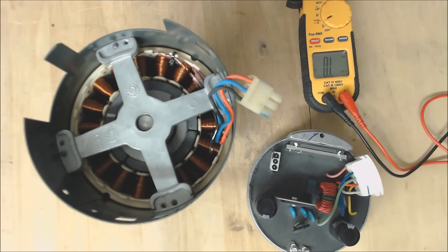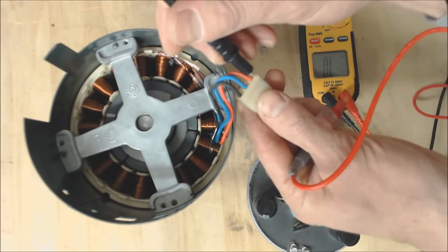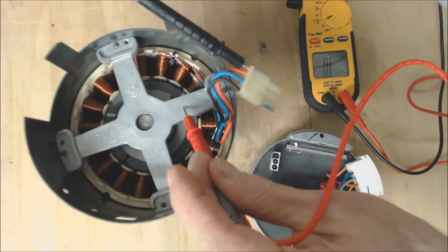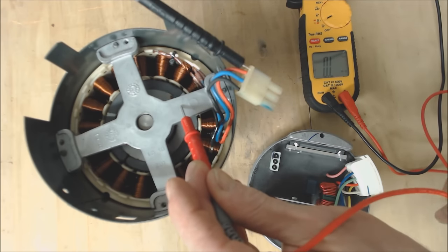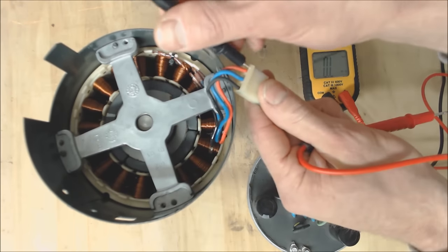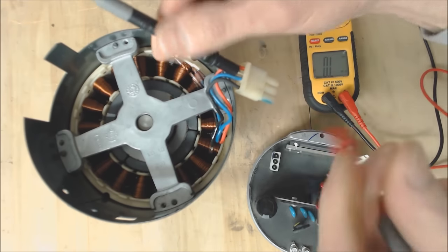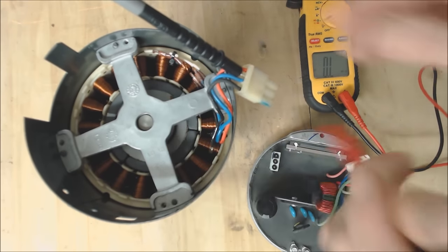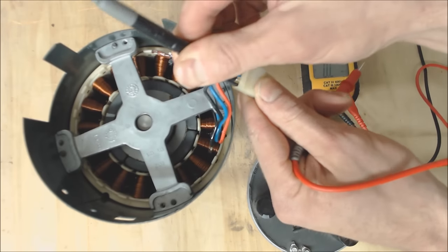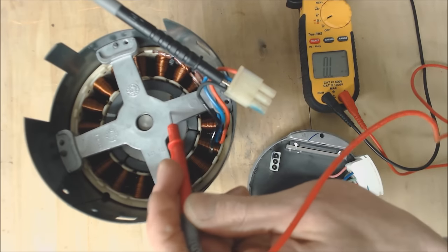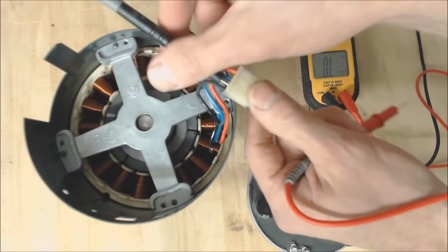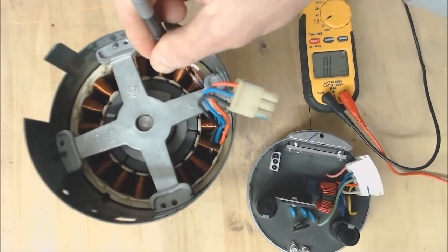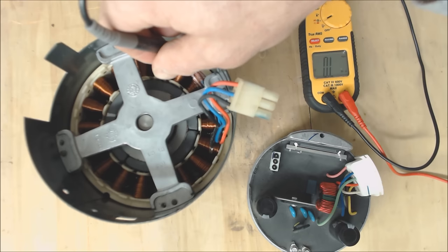The other thing that you want to check for is just to make sure that each of these windings are not grounded to the ground frame. So you see that we're reading open line which is over limit or open line and that's what you want. You don't want any resistance value with each of these windings. If you got 0.0 or some type of resistance value then that means that these windings in here have actually melted apart and are touching the ground frame.